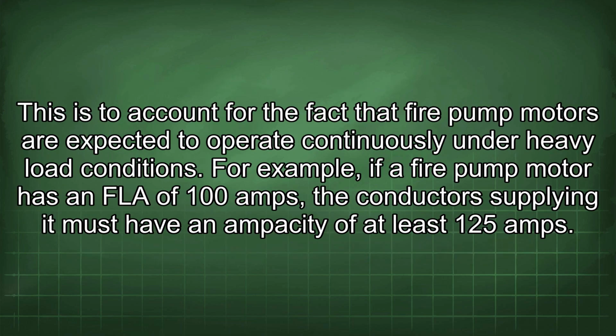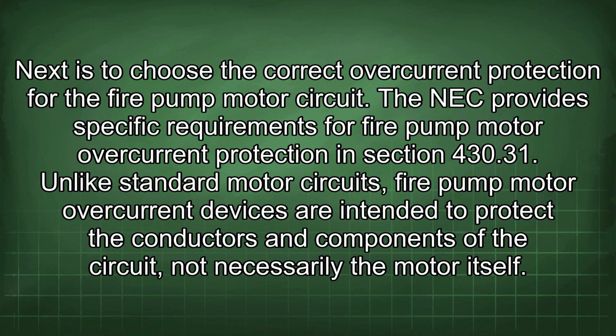This is to account for the fact that fire pump motors are expected to operate continuously under heavy load conditions. For example, if the fire pump motor has an FLA of 100 amps, the conductors supplying it must have an ampacity of at least 125 amps. Next is to choose the correct overcurrent protection for the fire pump motor circuit.